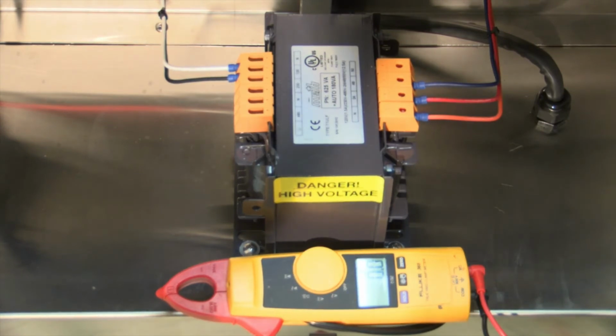Another common troubleshooting scenario is a blown fuse. Humidifirst suggests verifying if a fuse is good or bad by reading the voltage across it. Sometimes a fuse can blow and still allow continuity, so just reading continuity will fool you. Let's take a minute to look at the transformer and talk about the power structure inside the MistFree system.